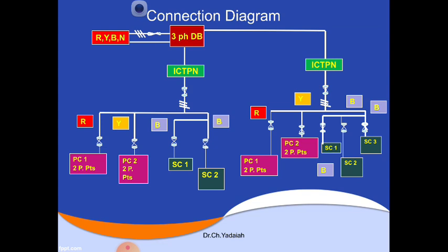So we get the total power P, and root 3 is a constant, and VL is the line voltage. In the case of the 3-phase supply, we take the input as 440 volts, and IL we are going to calculate, the unknown value. Cos phi in domestic supply, for NPDCL or CPDCL, we assume as a 0.85 lag power factor.